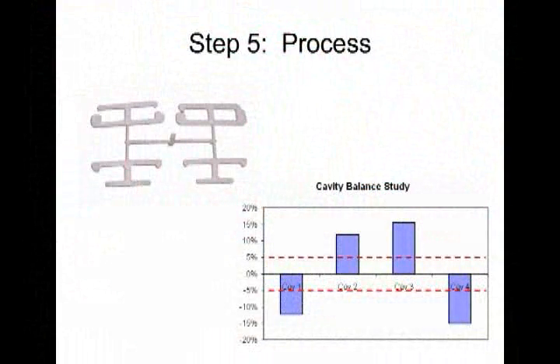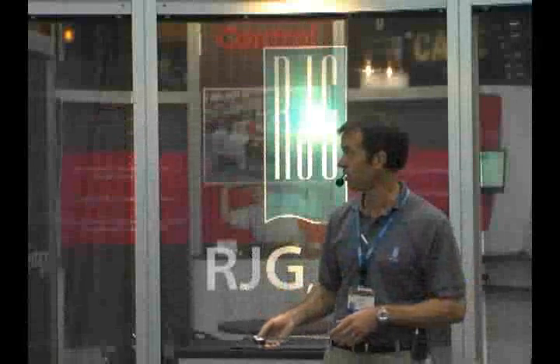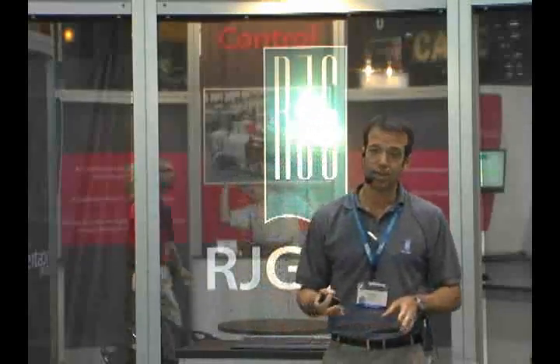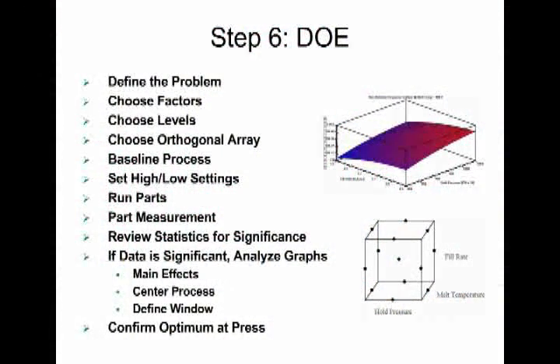Cavity balance study, of course — we've finished the IQ phase and we're doing the operational qualification. Now we need to know how well our balance design works in reality when we're running the mold. It's a very important step of the OQ. And then DOE — DOE is actually one of the very specific things called out in the FDA regulation: using DOE as a tool during the operational qualification.